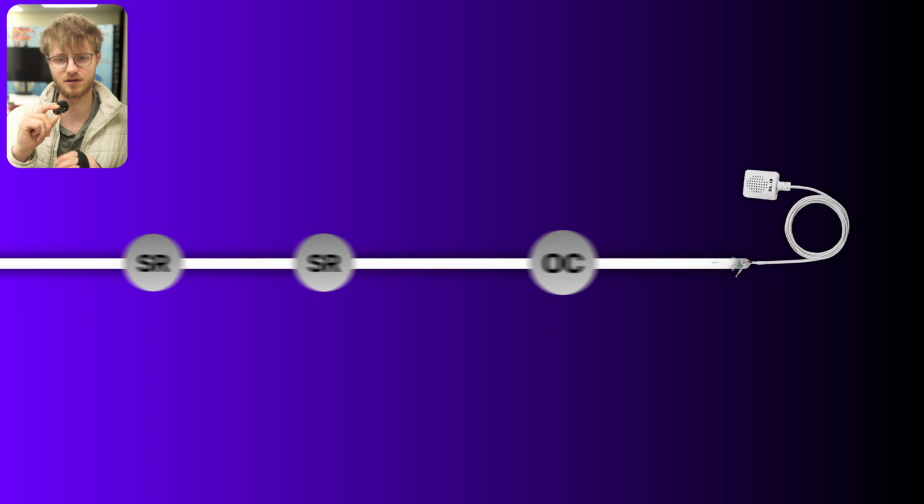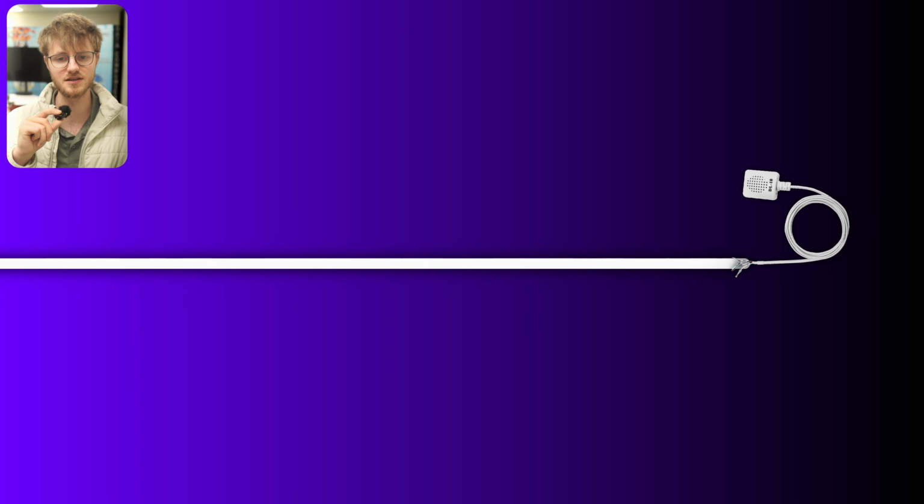Now, once you understand how devices are organized through the object dictionary, the next thing to understand is how data actually moves across the network. CANopen handles this in two separate ways depending on what kind of data it is. Real-time data like sensor readings and output commands move continuously at high speed, so the network always has an up-to-date picture of what every device is doing. But configuration and setup data moves separately on demand, so when you need to change a parameter or read detailed device information, that happens without interrupting the live process data already running on the network.